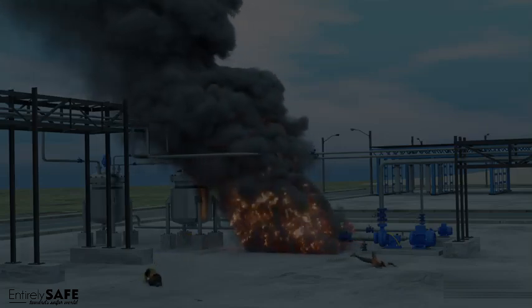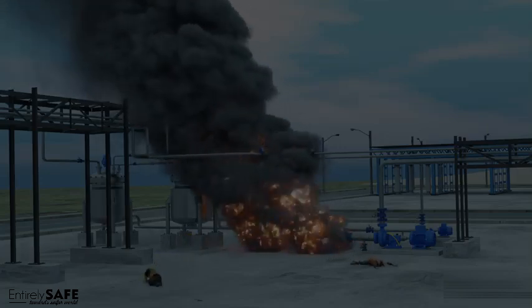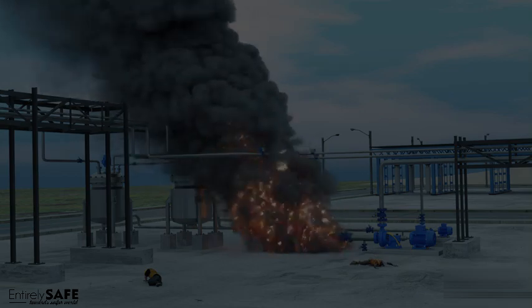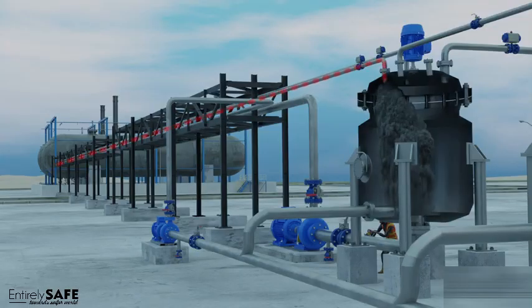It was estimated that 7 kilograms of hydrocarbon vapor could have caused the explosion. Some flammable vapor leaked from the nearby raw material tanks through the closed valves into the reactor and was ignited by a high-speed abrasive wheel, which was being used to cut through one of the pipelines attached to the vessel.